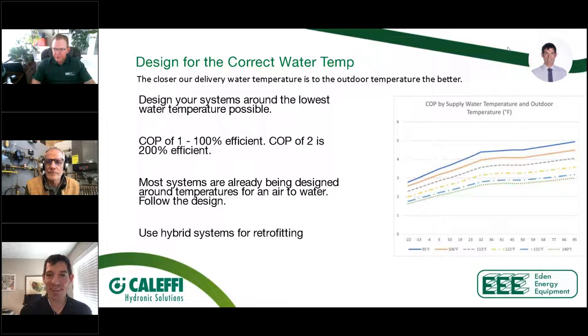If we're trying to run that thing out to 145 degrees to go through some undersized fin tube baseboard that's all covered in dog hair or something like that in the building, at best case, the efficiency is going to go way down, that we're getting closer to electric resistance heat, which is using a very expensive piece of equipment to do something that it shouldn't. That's really not what it's designed for.